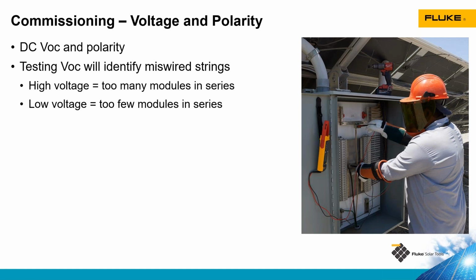Now, during the commissioning stage, we want to test voltage and polarity of our DC circuits of modules. Testing open circuit voltage, first we'll need to identify what the expected result is: the open circuit voltage of the module multiplied by the number of modules in the string. And then we can test voltage of our circuits.